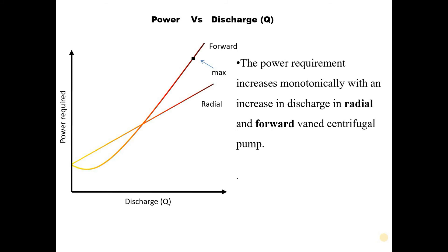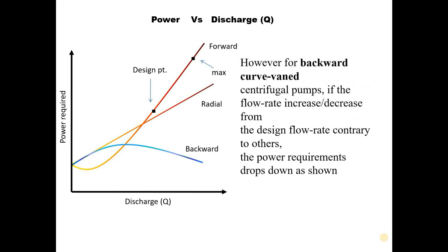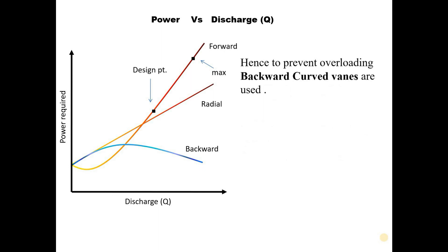On the other hand, if the pump is rated at the design point and the operating flow rate exceeds it, the power required will shoot up, causing overloading. However, for backward curved vane pumps, if the flow rate increases or decreases from the design flow rate, contrary to the others, the power requirement drops down. Hence, the vanes are curved backwards to prevent overloading of the impeller motor.